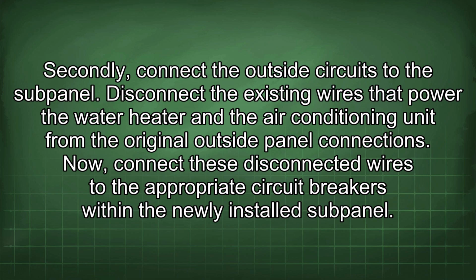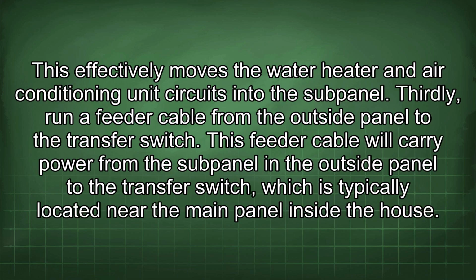Secondly, connect the outside circuits to the subpanel. Disconnect the existing wires that power the water heater and the air conditioning unit from the original outside panel connections. Now connect these disconnected wires to the appropriate circuit breakers within the newly installed subpanel. This effectively moves the water heater and air conditioning unit circuits into the subpanel.